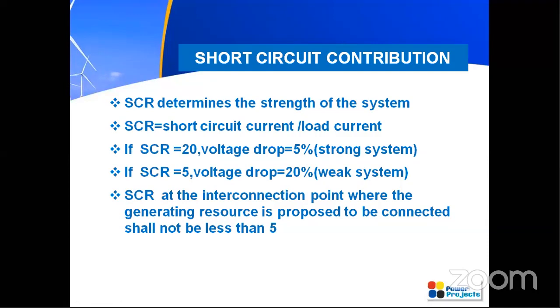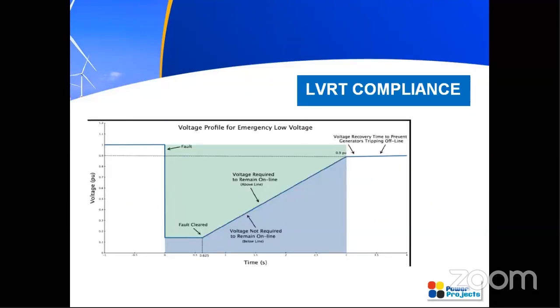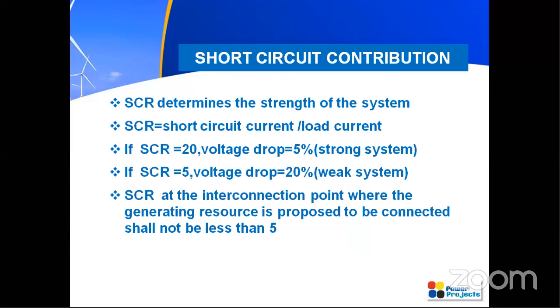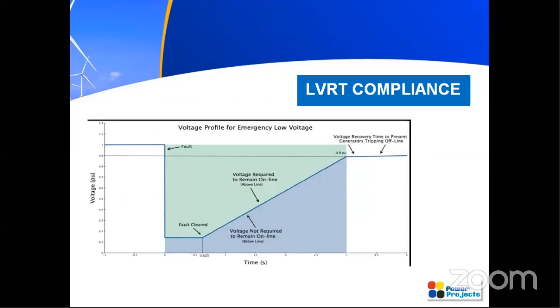Usually our wind plants and solar plants contribute very little short circuit current. That is why they stress the point that it should not be less than 5. Sorry, the ratio should not be less than 5. So it depends on your load current as well as your short circuit current.